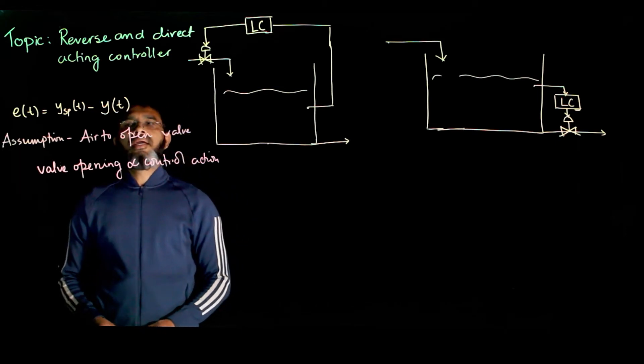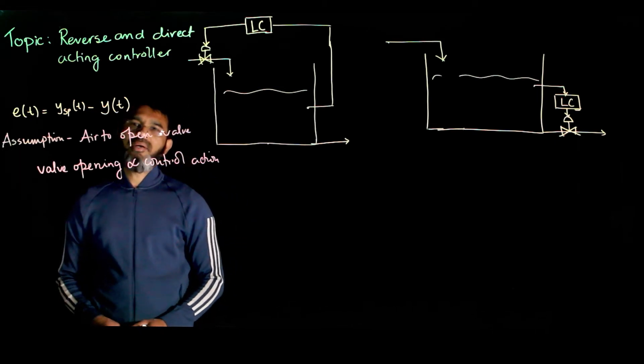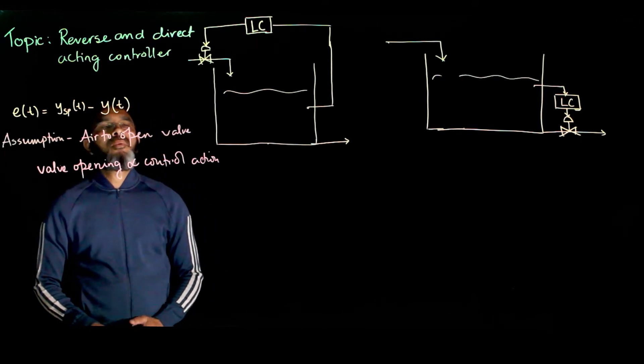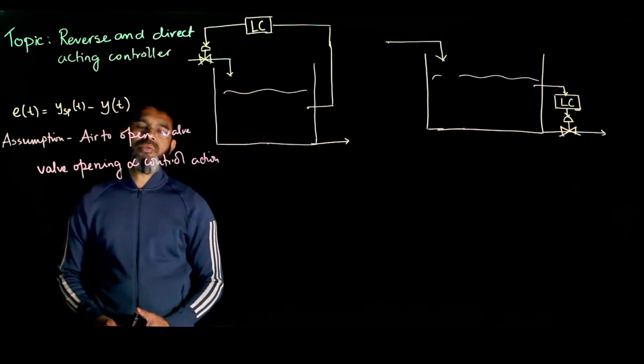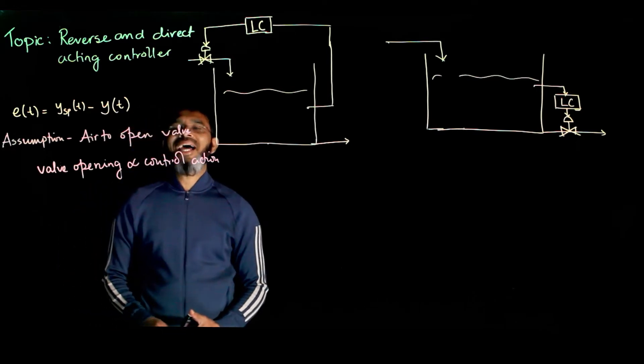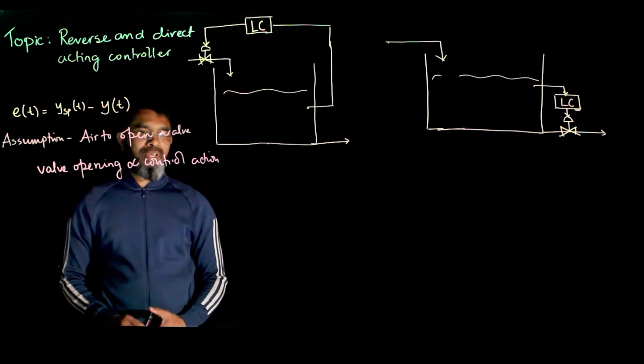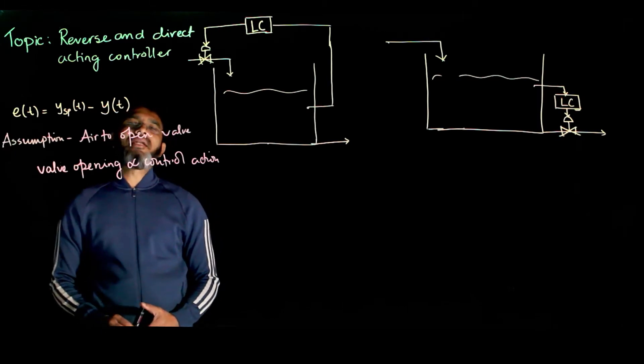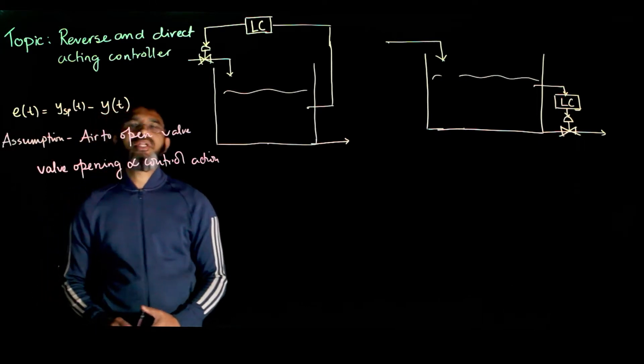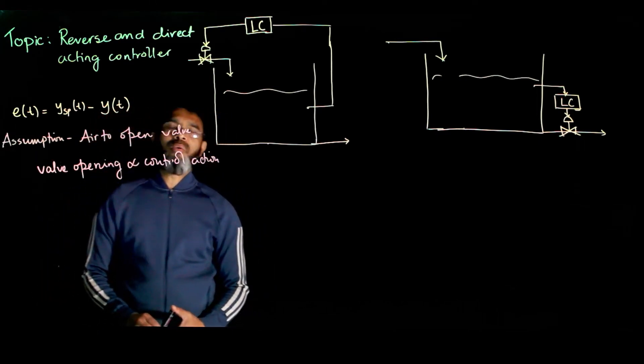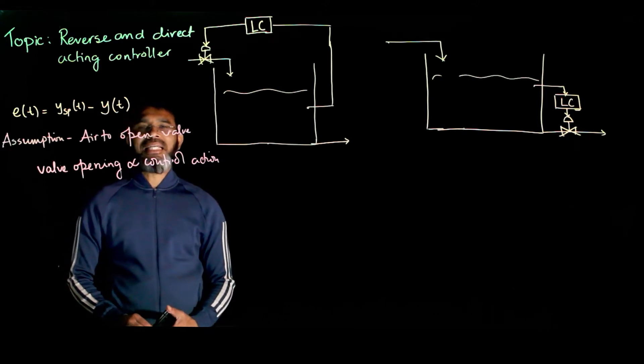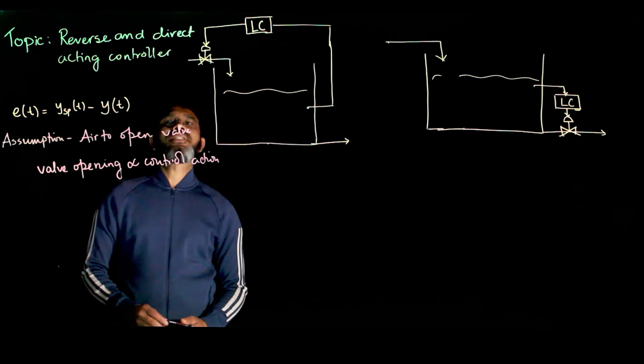The controller gain has a value and also a sign. In commercial PID applications and also in loop tuning software, it does not ask you for the sign of the controller gain. Meaning, if KC is supposed to be negative 12, you input the value as 12 and then you specify whether it is direct acting or reverse acting.